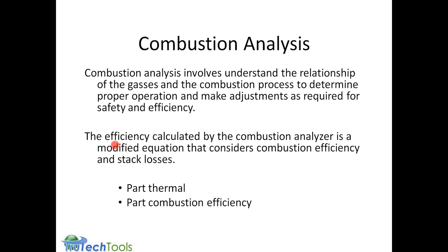The combustion efficiency that's calculated by the analyzer is a modified equation that considers part combustion efficiency and part stack losses. From the stack loss standpoint, that's how effective your heat exchanger is and how much excess air you have moving. It's a little complex, but basically it's part thermal, part combustion efficiency. All the major manufacturers run their combustion equations about the same way. So when you compare one to the other, they may be off by a couple points, but they're all in the same ballpark in terms of indicating combustion efficiency.